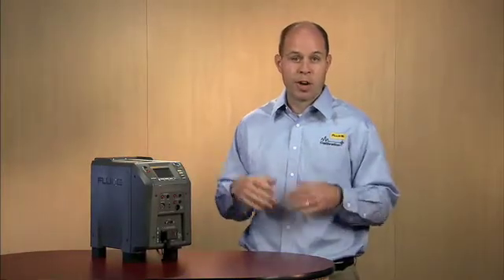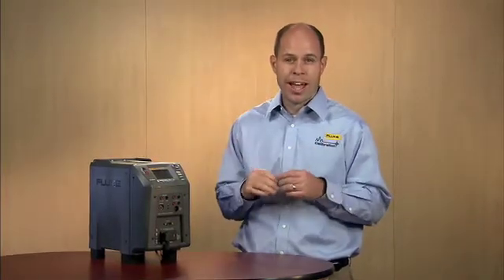With the field metrology wells, you're able to program up to eight different temperatures. At each one of those temperatures, you will define a soak time in which you will soak over that period of time.